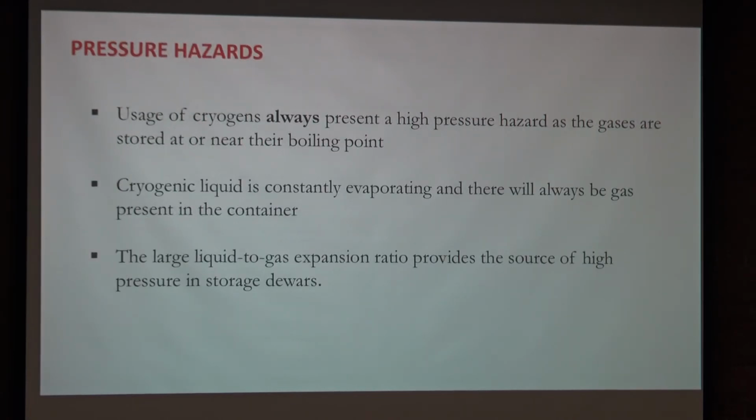There is the hazard of pressure. Since these liquids are always near their boiling point, they will continuously evaporate. You want to make sure that the dewar vessel you're using provides a means for the evaporated gas to escape safely.